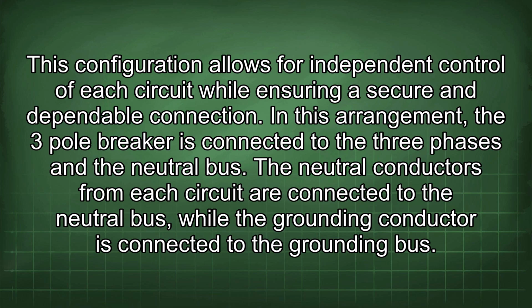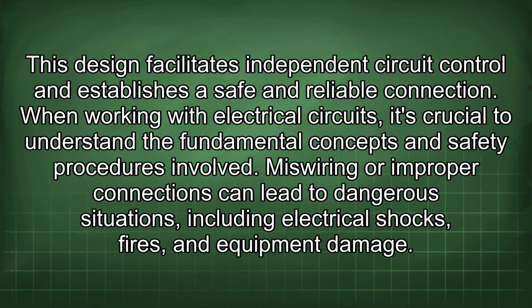In this arrangement, the 3-pole breaker is connected to the three phases and the neutral bus. The neutral conductors from each circuit are connected to the neutral bus, while the grounding conductor is connected to the grounding bus. This design facilitates independent circuit control and establishes a safe and reliable connection.